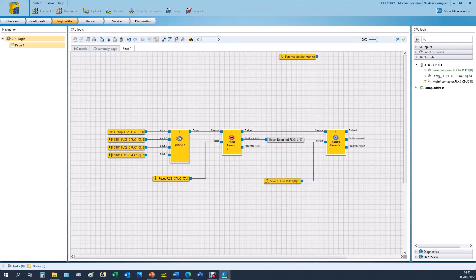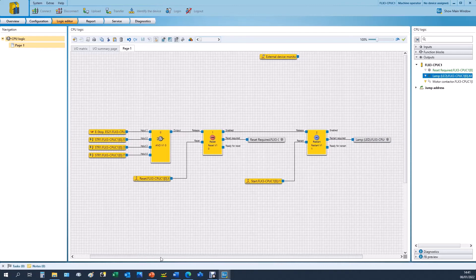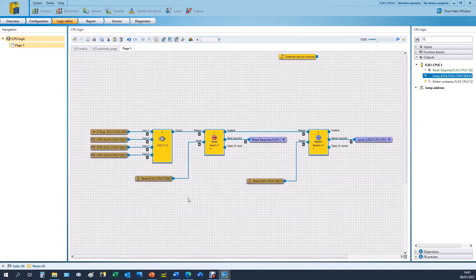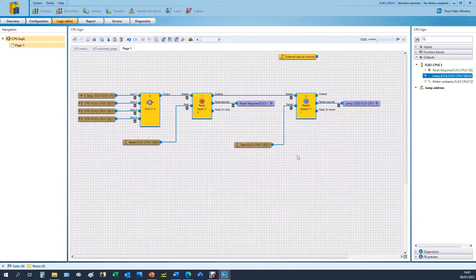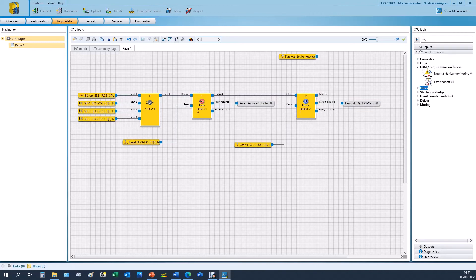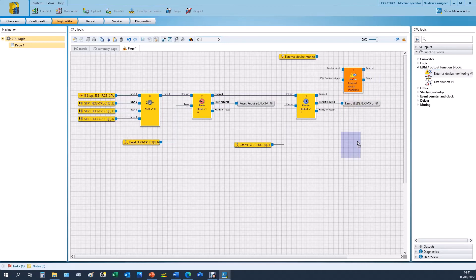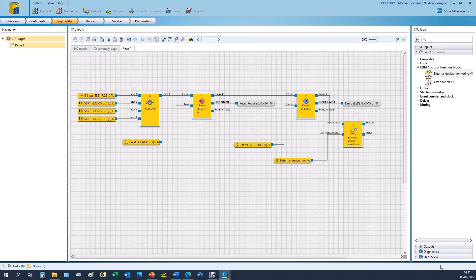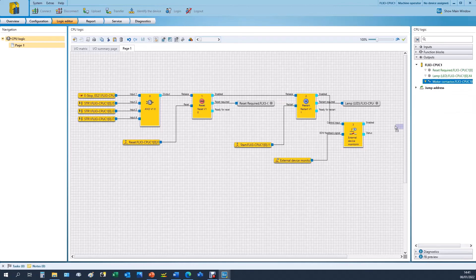Then we have the other lamp which we may want to signify that a restart is required, so I've added that to the function block. If you want to move all of the logic you can highlight all of it and move it around the page. And then finally our enabling signal to the contactors. We would also want to have some external device monitoring of those contactors, so we can have our feedback going into our EDM feedback and our enable to the control input. And then all we need to do finally is connect the motor contactors, which are a dual channel bit, to our enable output.